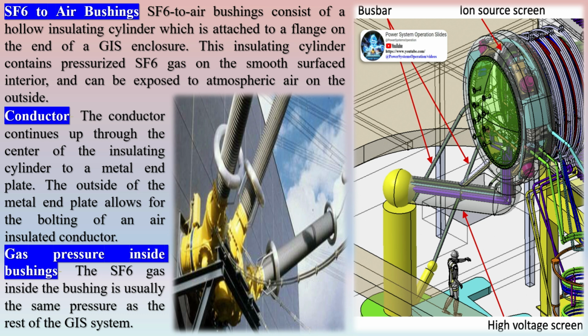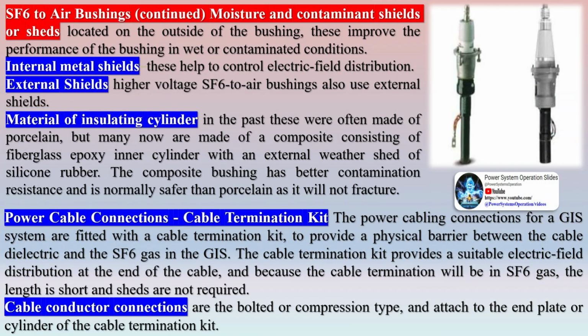SF6-to-air bushings consist of a hollow insulating cylinder which is attached to a flange on the end of a GIS enclosure. This insulating cylinder contains pressurized SF6 gas on the smooth-surfaced interior and can be exposed to atmospheric air on the outside. Moisture and contaminant shields: sheds located on the outside of the bushing improve the performance of the bushing in wet or contaminated conditions. Internal metal shields help to control electric field distribution. External shields: higher voltage SF6-to-air bushings also use external shields.